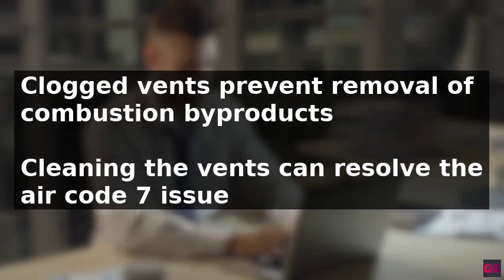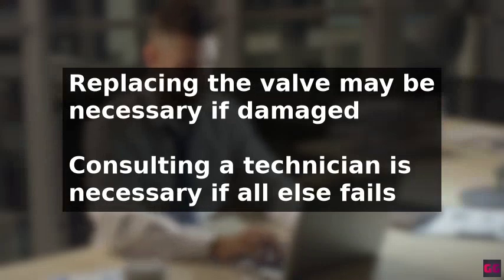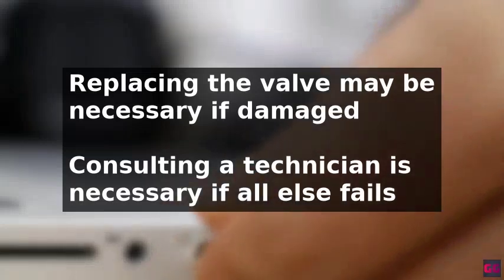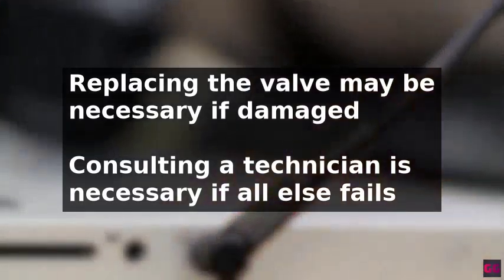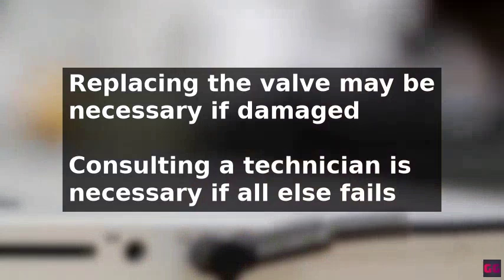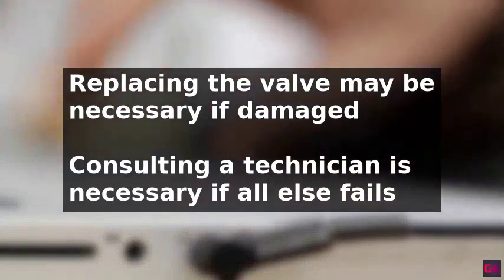If neither of these steps works, the gas control valve may need to be replaced. This involves inspecting the valve for dirt or physical damage, cleaning it if necessary, or replacing it if damaged. If none of these solutions work, it may be necessary to consult a qualified technician for further assistance.